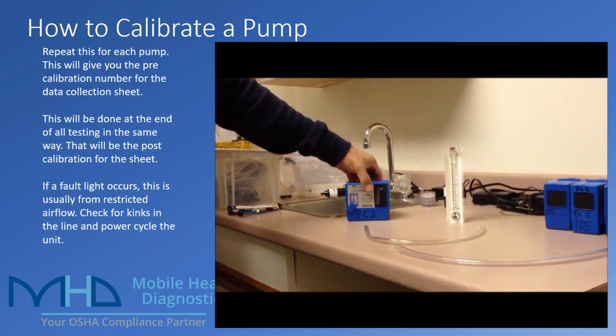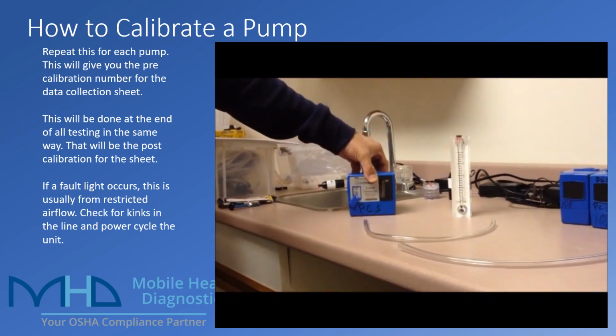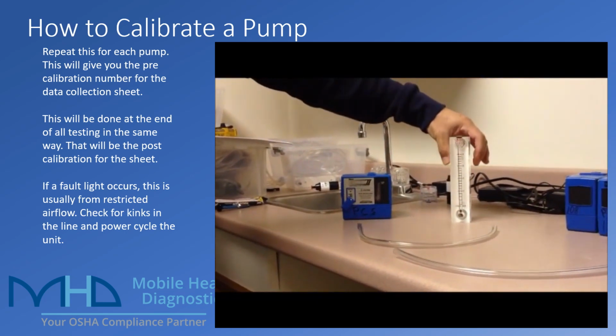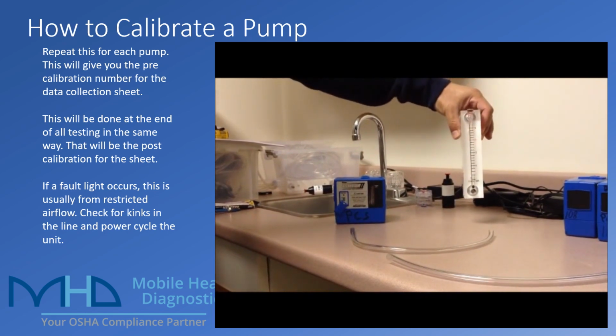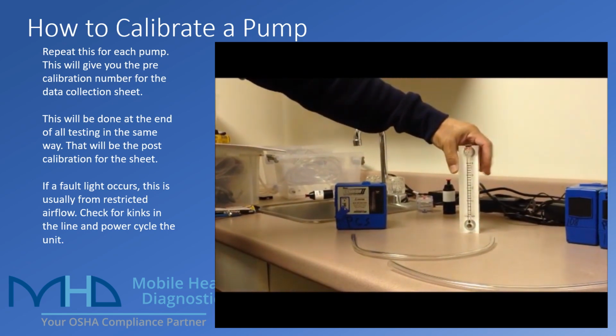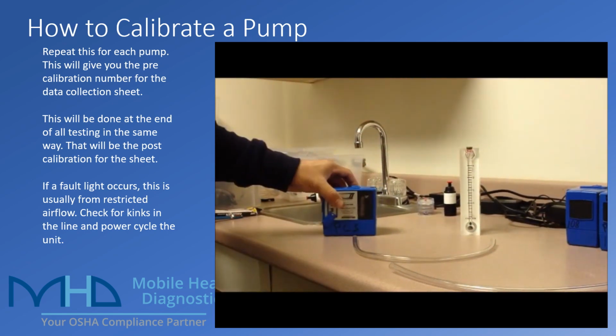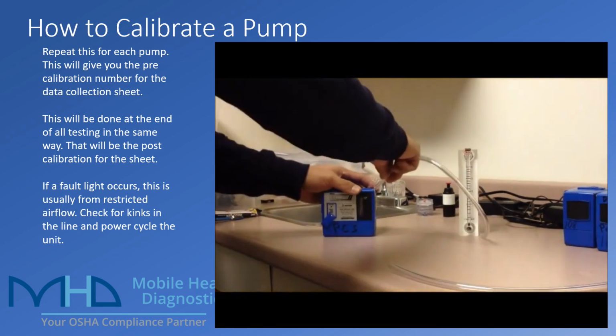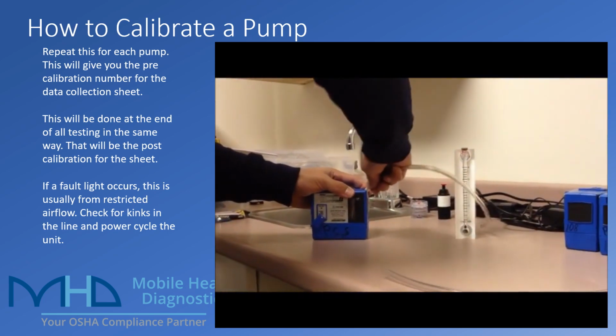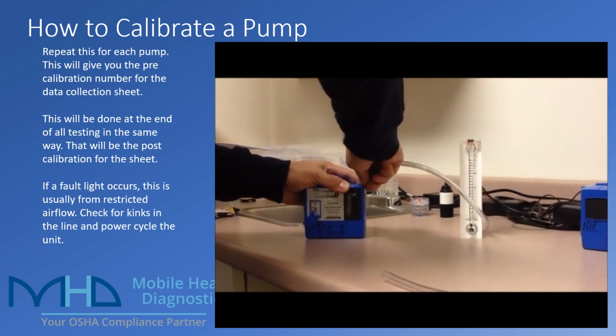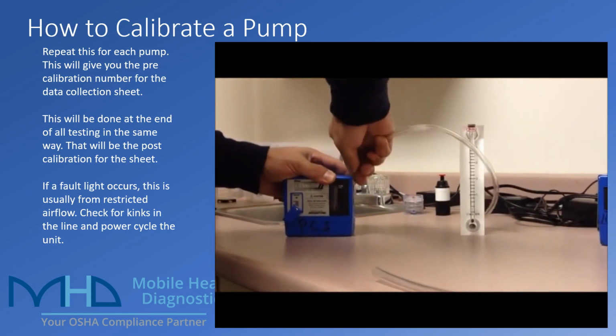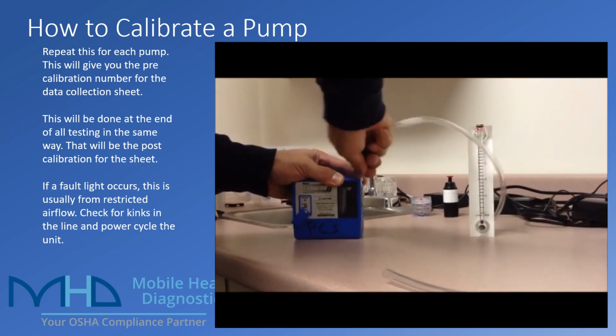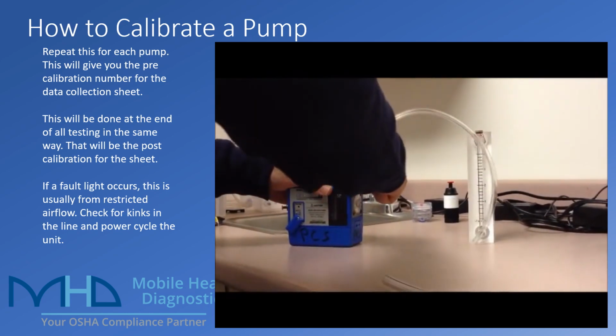You can see that a little bit closer up there. And then finally, you're going to take the other end of that pump and attach that to the top brass fitting on the actual calibrator itself. So once that's all set up, then we'll be powering on the pump in order to check and verify that the calibration is correct.